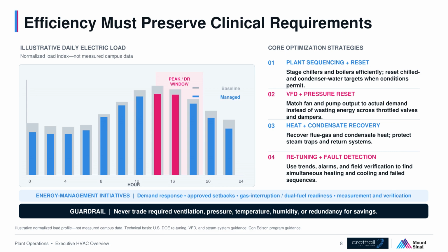Retune sequences and use fault detection to find simultaneous heating and cooling, failed resets, and sensors or actuators that lie. Demand response, approved non-critical setbacks, gas interruption readiness, and dual fuel capability can add flexibility. But prove outcomes with measurement and verification. The load curve shown here is illustrative, not measured campus data. The actual portfolio is roughly $43 to $44 million per year, with electricity dominant, so peak demand, chiller dispatch, fan power, pump power, and tower operation deserve attention. Reliable operation and good measurement are the foundation of credible savings and emissions reduction.